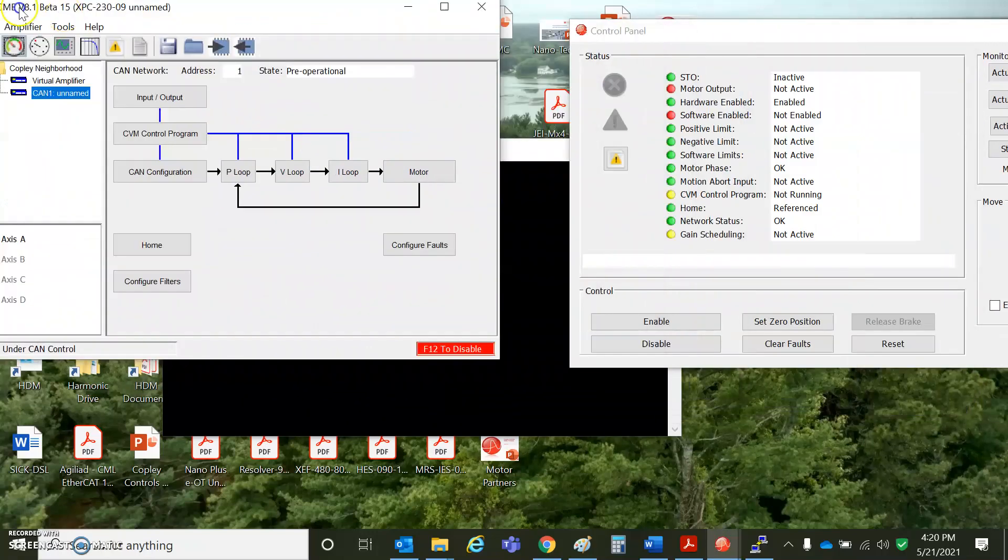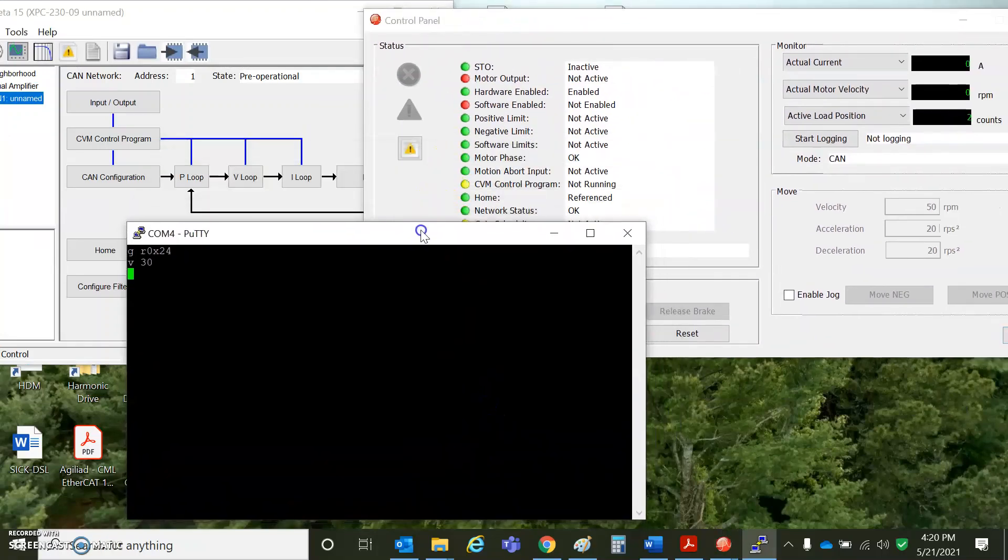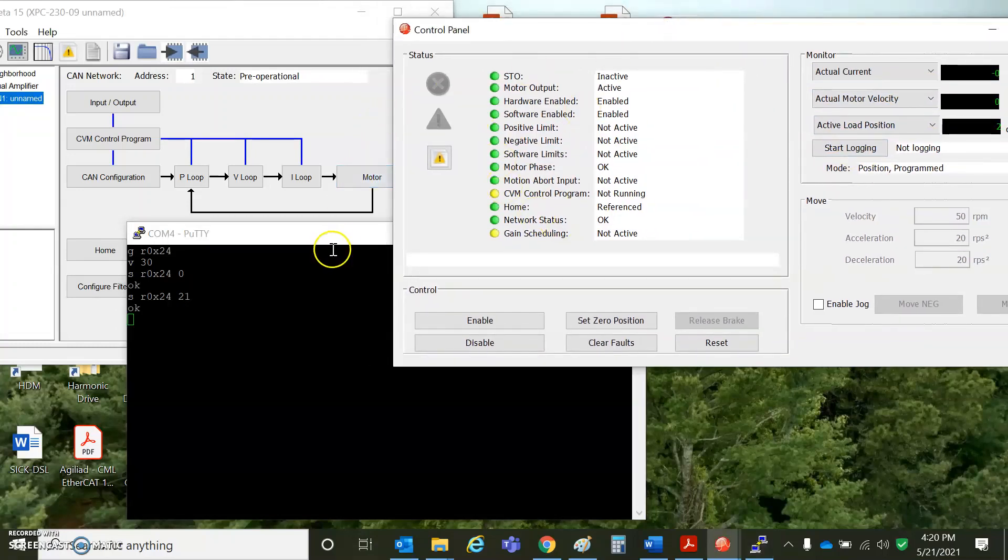Let's keep an eye on the control panel and we're just going to affect the mode of operation. You can see it's in a CAN mode, so it's waiting for a CAN master. Set r0x24 to 0 — that is the mode of operation disabled. Set r0x24 to 21 for servo, or 31 for steppers; this puts it in position program mode. It's all enabled — all green lights.